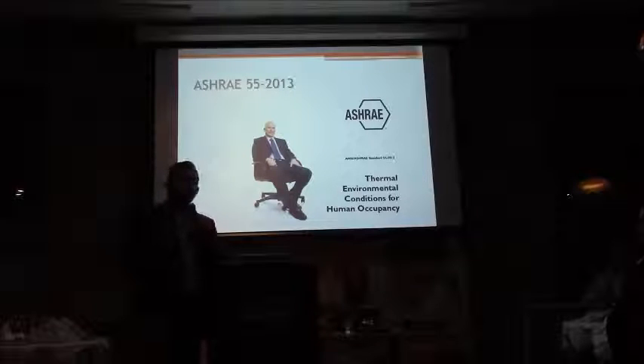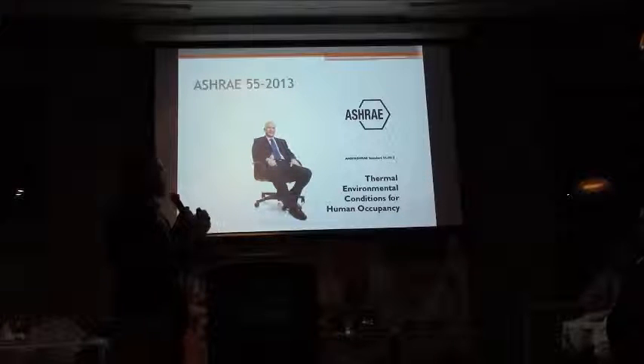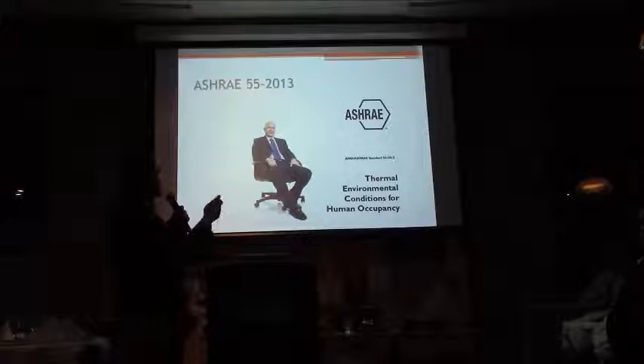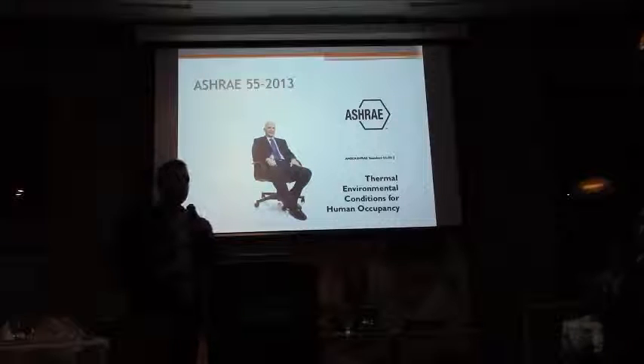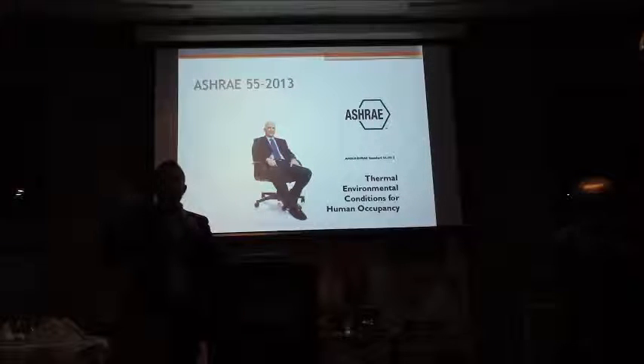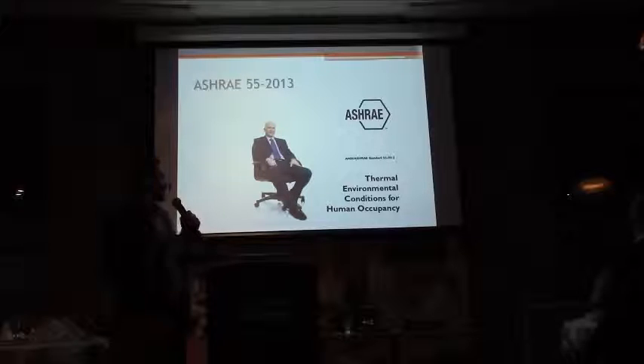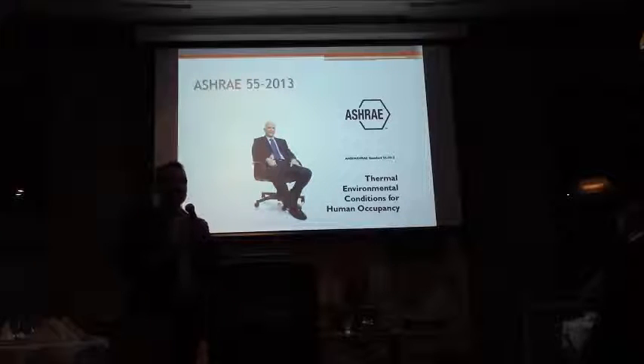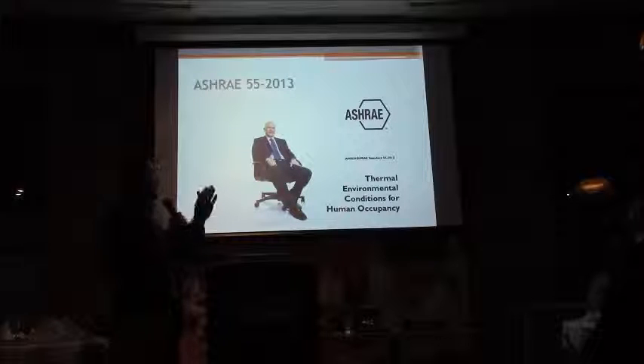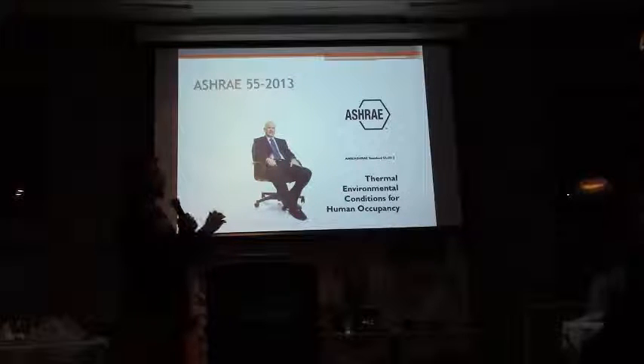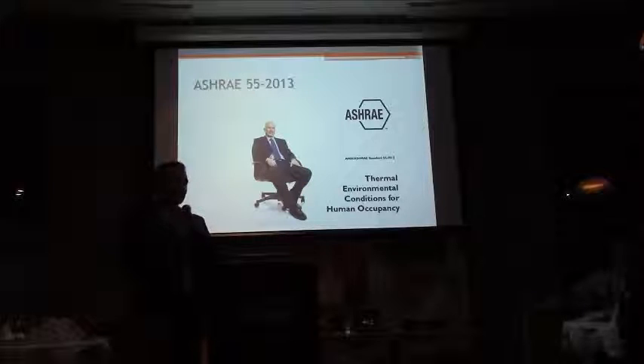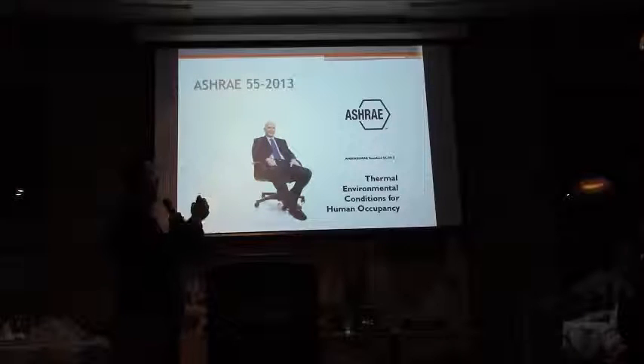So let's continue talking about comfort. This is ASHRAE Standard 55. The latest edition of it is the 2013 version. So that's the last edition of the ASHRAE 55 standard. And this is the standard that discusses comfort. Anything related to velocities, temperatures, anything related to comfort is inside that standard. And like I said, 30 feet per minute earlier. Let's see what ASHRAE 55 mentions in terms of velocities.